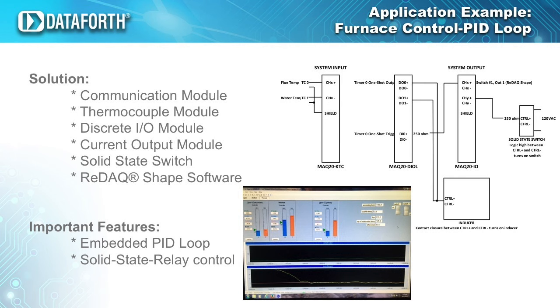The PID controller settings accessed through the controller faceplate are extensive and readily at hand, including the adjustable auto-tune. These settings can all be made on the fly. The auto-tune algorithms correctly stimulate the system, read the response, and provide the required coefficients for optimum process tune. This application displays features of the MAQ20 that could be interesting in other PID loop applications in terms of utilized features, cost, compact size, ease of implementation, and reliable 24/7 use.